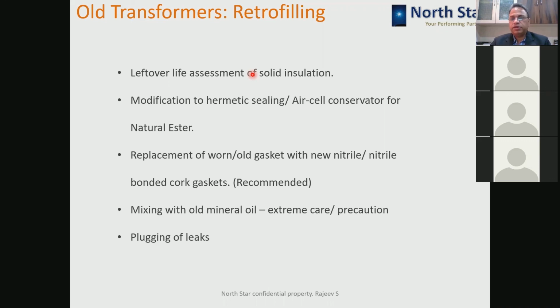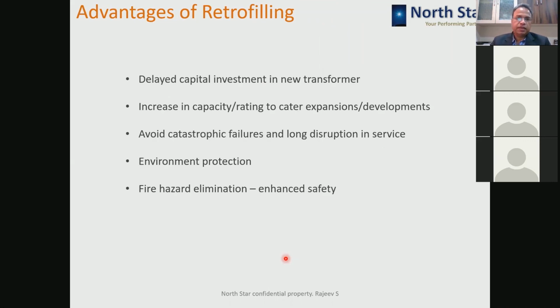And then all the leaks are to be plugged before going for the retrofilling. So retrofilling is very simple, very easy to do, and with a lot of advantages, like delayed capital investment in a new transformer. The transformer which you could have replaced within the next 2 or 3 years, by doing the retrofilling you can extend that replacement time maybe another 6 to 7 years, 8 years, or even 10 years. So you are delaying capital investment.